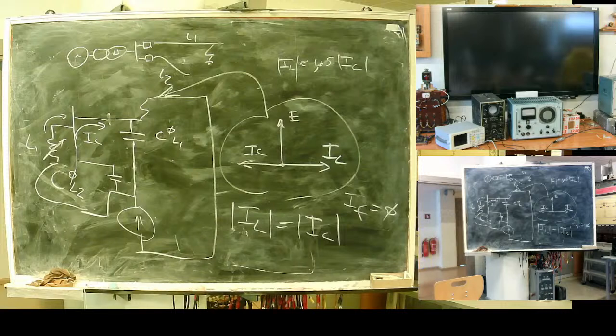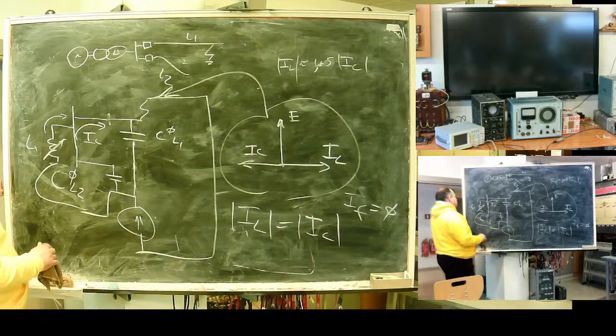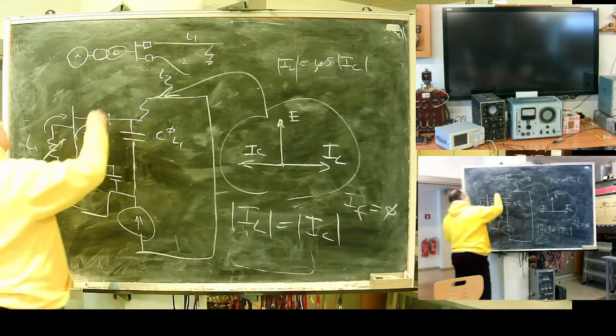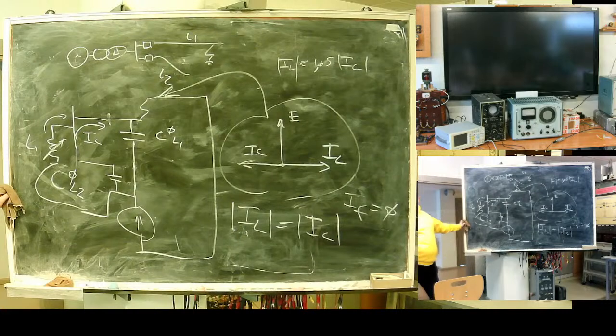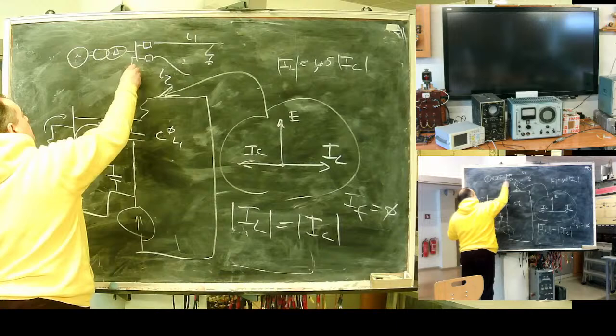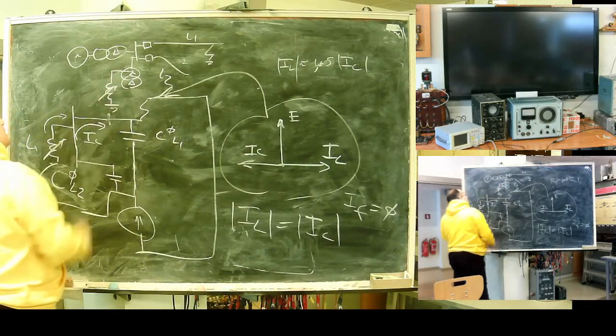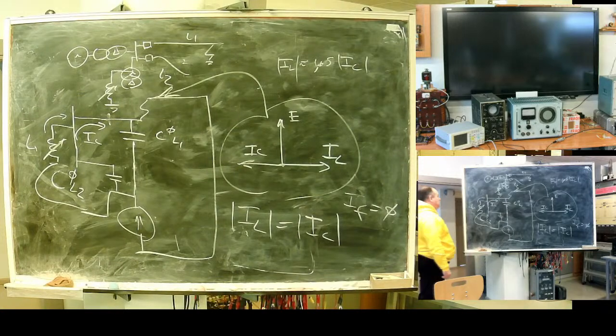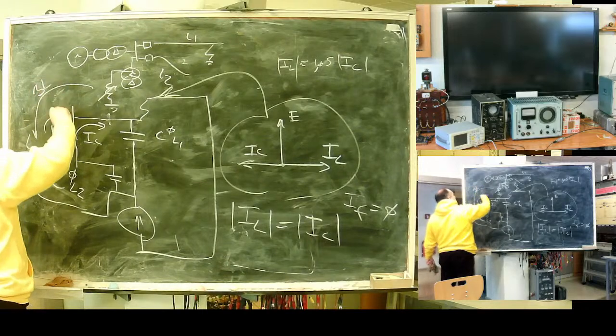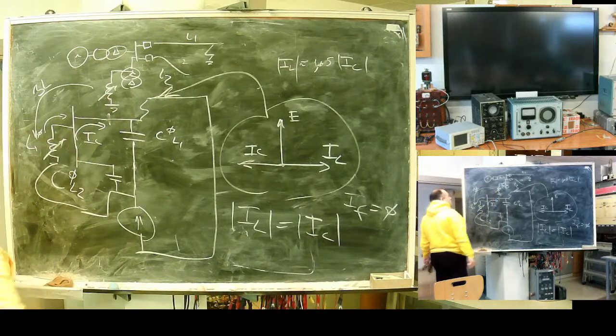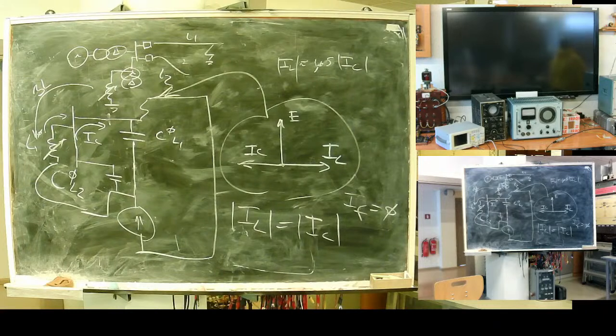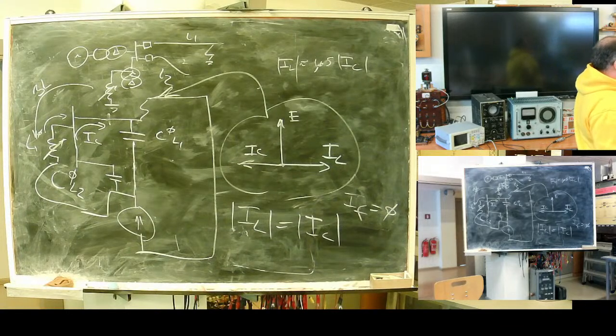But here is one problem. BTW, I need to draw how it's done. How can we attach something to neutral when we have no neutral? It's done with auxiliary transformer. It's done by creating an artificial neutral. And this one is triple. So it's in 0 sequence, triple inductance of this coil. This is how it's done. With the help of special neutral, artificial neutral transformer. Small transformer, 25-50 kW. Artificial neutral.